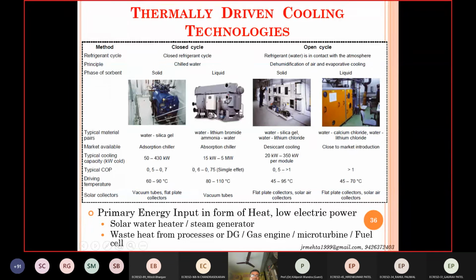So what you see is that the absorption systems are not available in very small sizes, right? Small sizes are generally not viable because you have to maintain a very high level of vacuum in such systems, or if it is ammonia water, then it's a pressurized system, right? So the COP is given, and what are the driving temperatures required in such systems. This is only for single stage. You need this temperature, right? If you want to go for double effect or even triple effect, available now, then the temperatures required would be much higher.